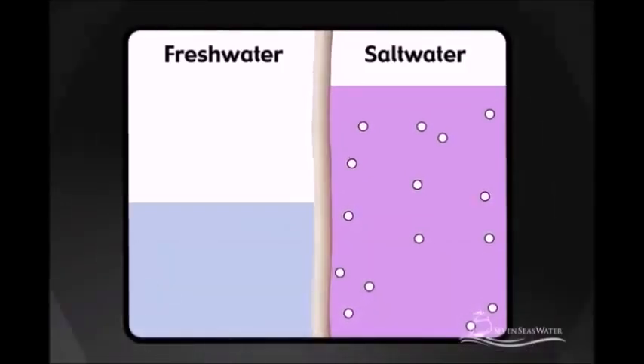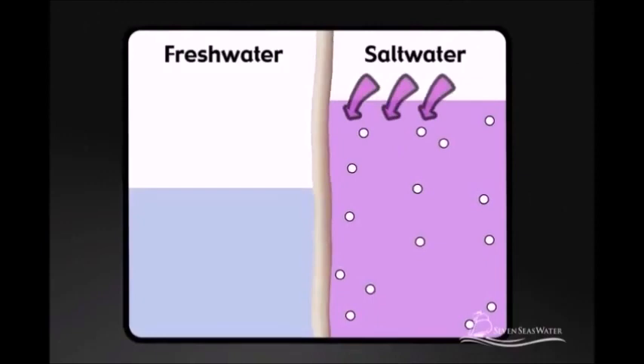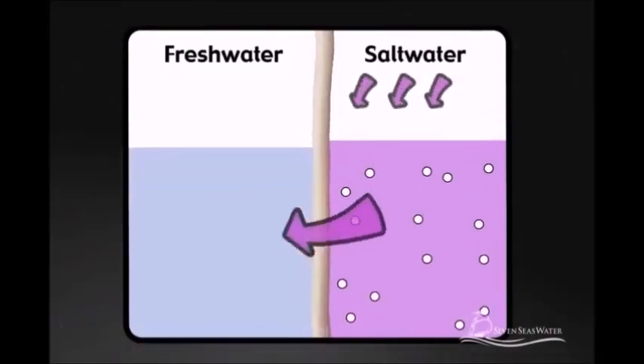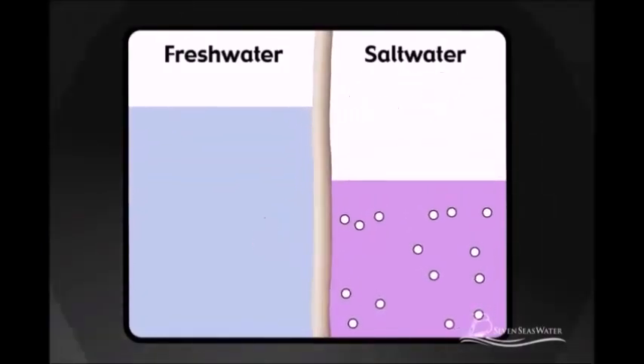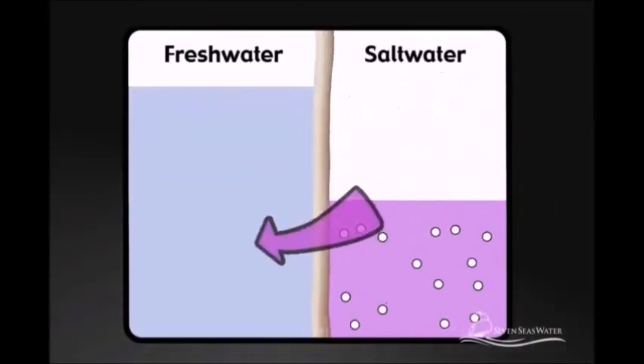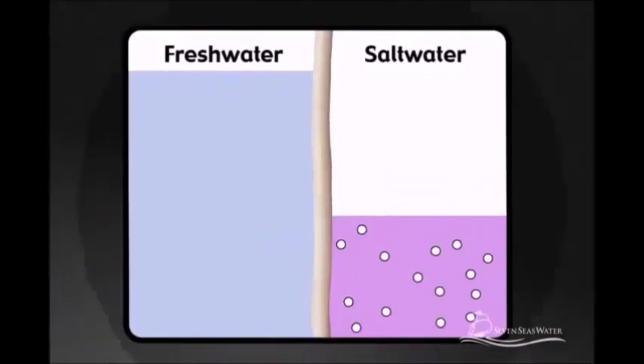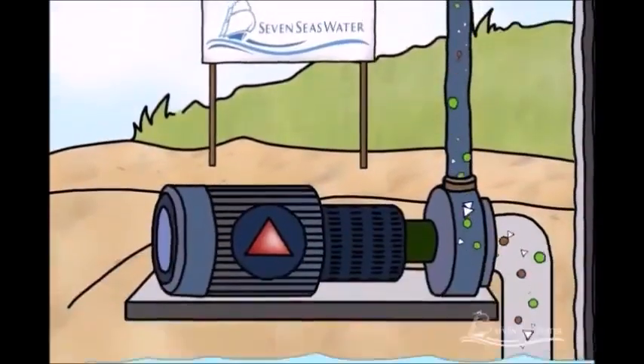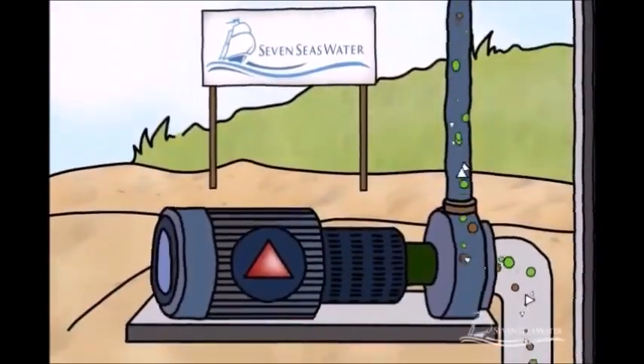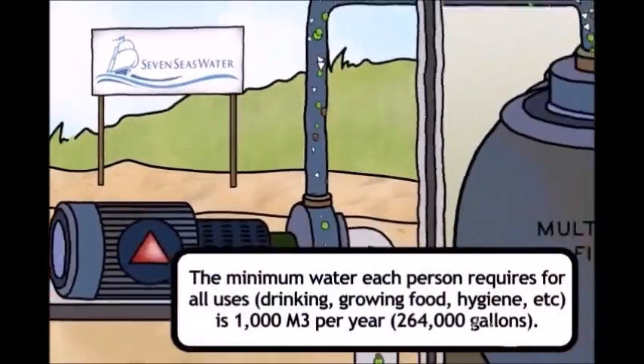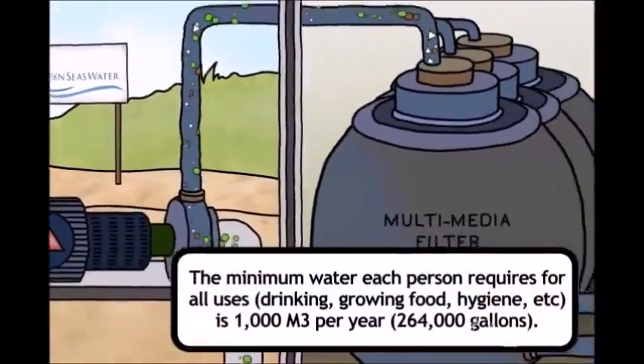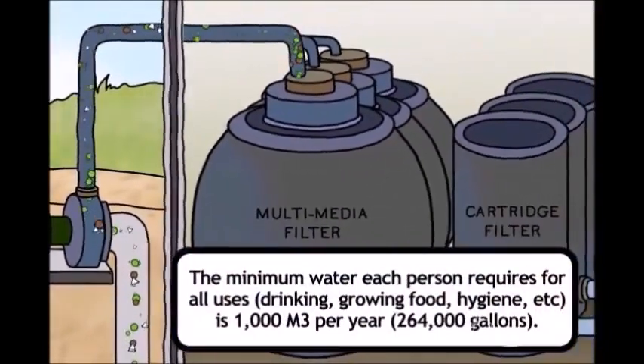Reverse osmosis is when the opposite occurs. By pressurizing the concentrated solution — the seawater — we are able to force water molecules to pass from the salty seawater solution through the membrane to the fresh water. To protect the reverse osmosis membranes from becoming clogged by solid particles that can be suspended in the seawater, the seawater is filtered before passing through the membranes.